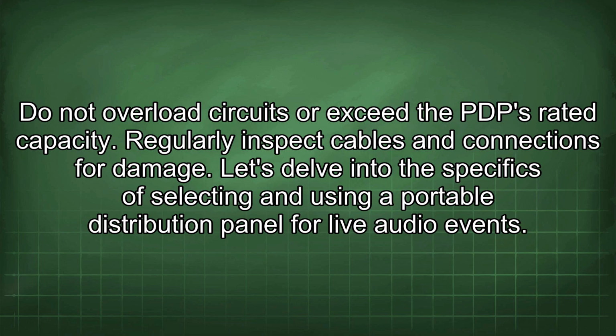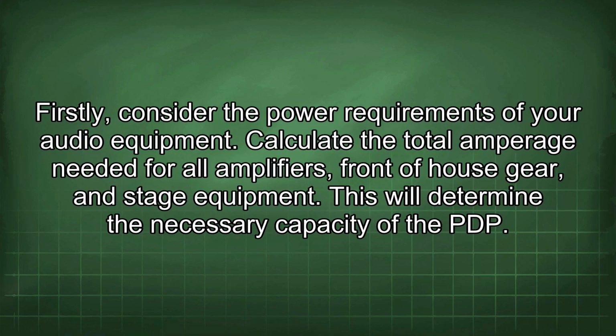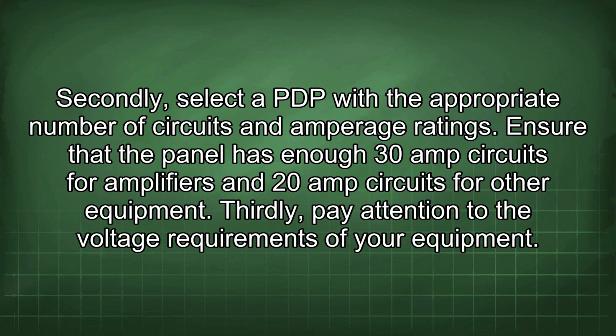Let's delve into the specifics of selecting and using a portable distribution panel for live audio events. Firstly, consider the power requirements of your audio equipment. Calculate the total amperage needed for all amplifiers, front-of-house gear, and stage equipment. This will determine the necessary capacity of the PDP. Secondly, select a PDP with the appropriate number of circuits and amperage ratings. Ensure that the panel has enough 30 amp circuits for amplifiers and 20 amp circuits for other equipment.